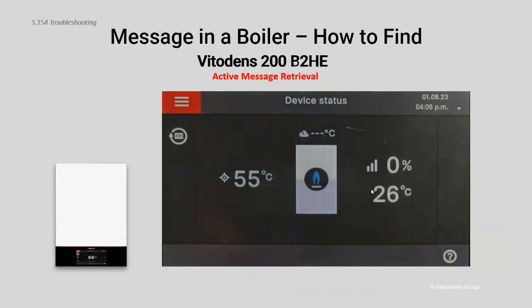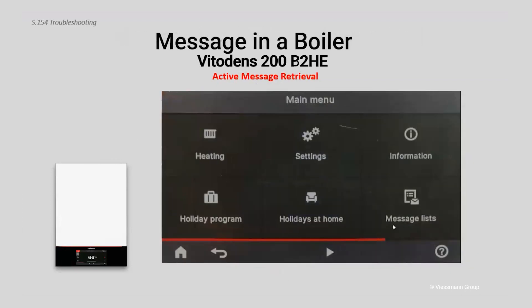The 200 boiler is a little different — the screen is different and navigation is a little different. It's a full touchscreen on the 200. If I want to retrieve an active message, I'm going to hit the menu key on the top left-hand corner. Down in the bottom right corner you'll see 'message list' — active messages are stored right there for navigation. Simply hit the menu key, then at the bottom right you'll see a message list.